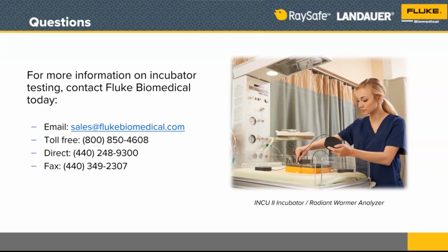Okay, so warm-up time. It's a good thing to discuss because we don't want the incubator to be warmed up before we start our testing. We start with it at room temperature, whatever room temperature is. So we really don't care if the room's a little colder or a little warmer than average. Whatever that room temperature is, that's where we're going to start. And what we want to do is have our infant incubator analyzer inside the incubator, and then we want to turn the infant incubator on and begin the heating cycle. We want to measure between the time that the heater first turns on and the time it takes to reach 11 degrees C above ambient or room temperature. And at that point, we document the amount of time that it took.